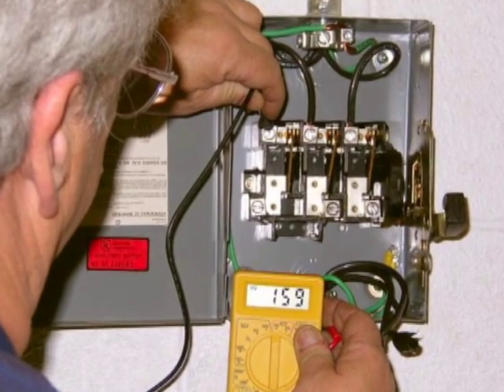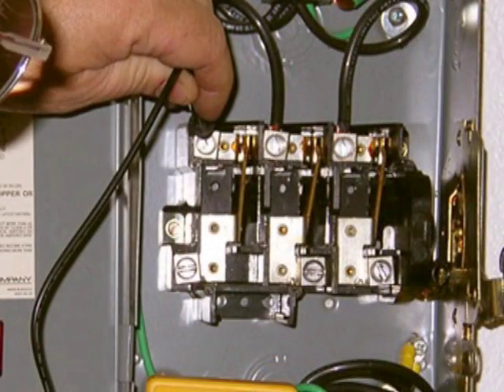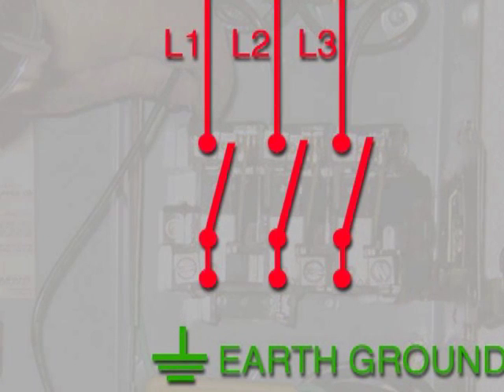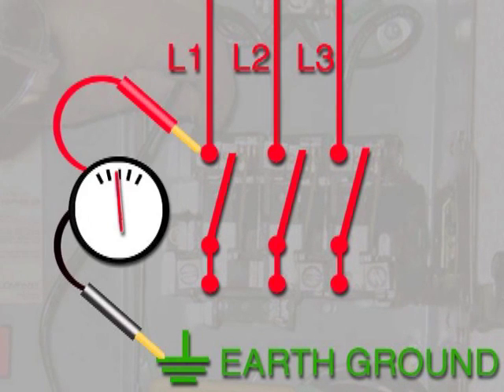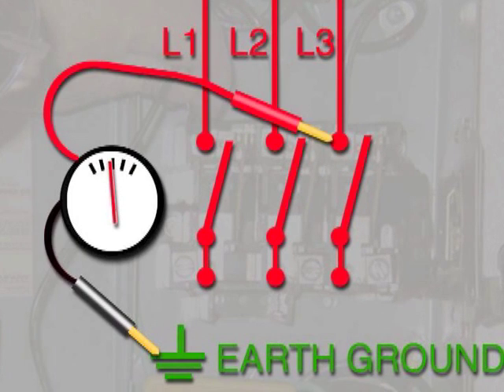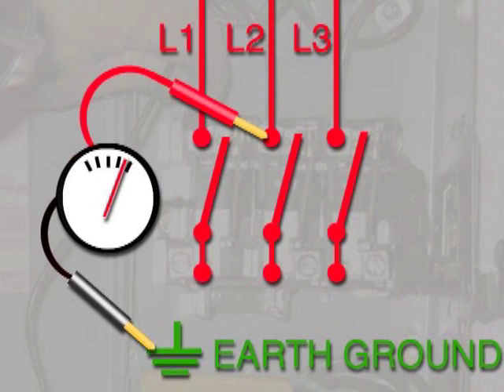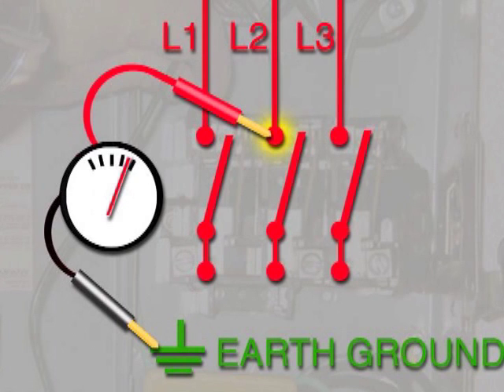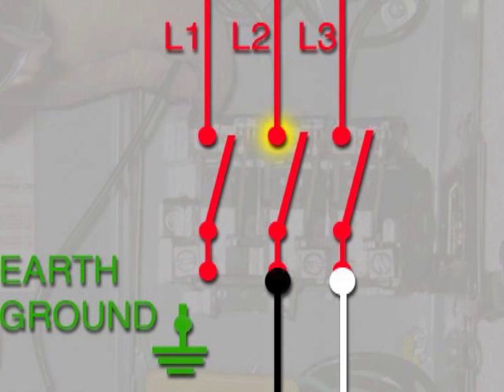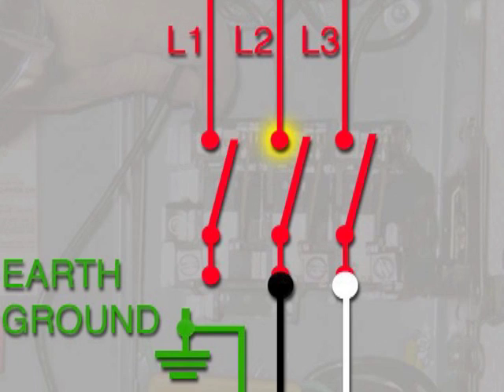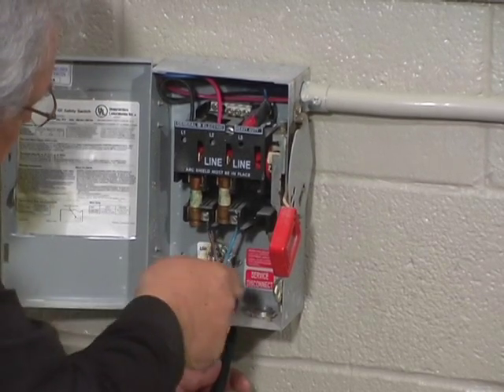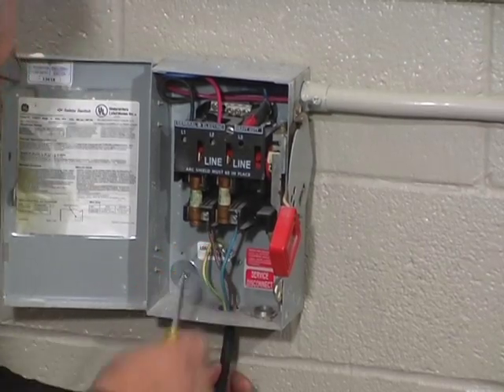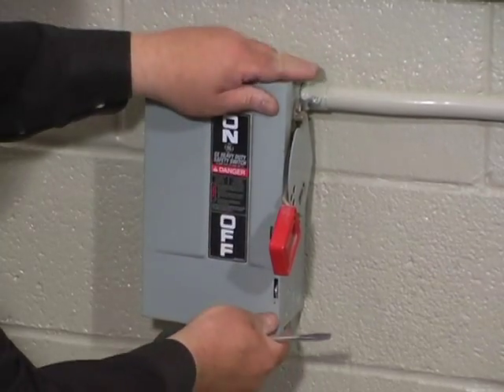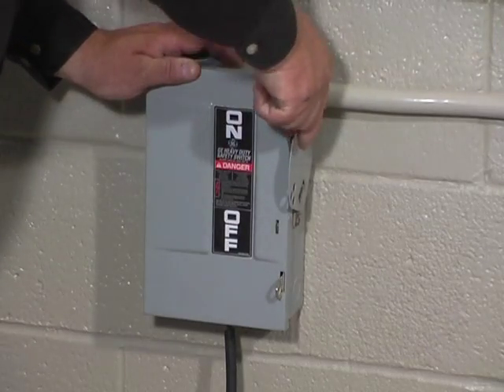Here's a special tip for those 240-volt machines. In a 3-phase electrical system, you have one leg, that's a phase, that is higher than the other two. You can measure the voltage between each leg to ground to find out which is the higher voltage. Use this leg and one of the lower voltage legs for best performance. The third wire is a green or a green with yellow stripe. Connect this wire to the earth ground lug provided in the disconnect box. Turn on the main disconnect.